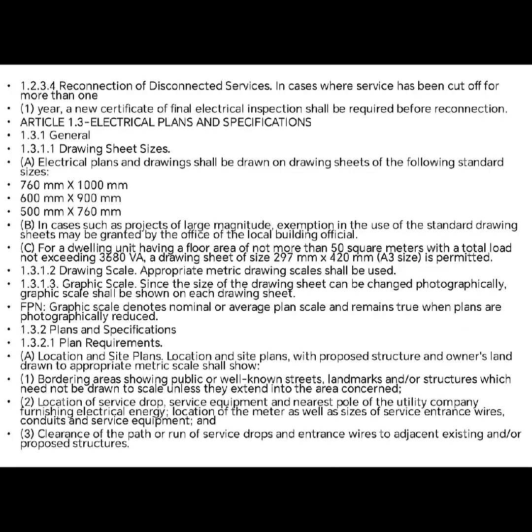1.3.2.1 Plans requirements. A. Locations and site plans. Location and site plans with proposed structures and owner's land drawn to appropriate metric scale shall show: 1. Bordering areas showing public or well-known streets, landmarks, and/or structures, which need not be drawn to scale unless they extend into the area concerned. 2. Locations of service drop, service equipment, and nearest pole of the utility company furnishing electrical energy, as well as sizes of service entrance wires, conduits, and service equipment. And 3. Clearance of the path or run of service drops and entrance wires to adjacent existing and/or proposed structures.